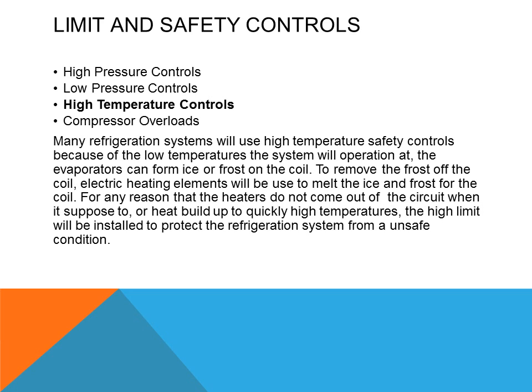Many refrigeration systems will use high temperature safety controls because of the low temperature the system will operate at. The evaporators can form ice or frost on the coil. To remove the frost off the coil, electric heaters will be used to melt the ice and frost off the coil. For any reason that the heaters do not come out of the circuit when they're supposed to, or build up heat too quickly, building up high temperatures, the high limit will be installed to protect the refrigeration system from an unsafe condition.